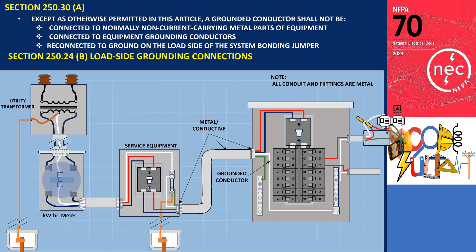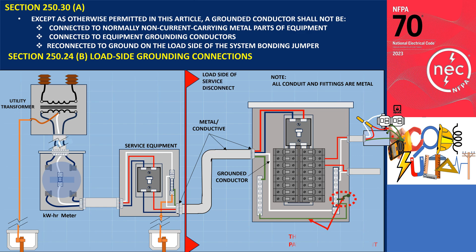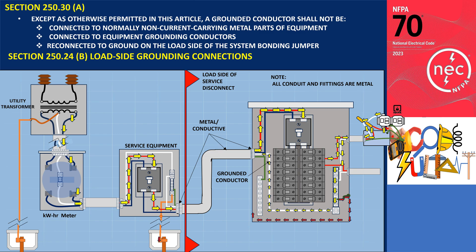This rule has been specified in section 250.24. This is not allowed because it introduces parallel paths for neutral current on the load side. When the grounded conductor, typically the neutral, is connected to the panel enclosure or any conductive metal components of electrical equipment at the load side of the service disconnect, it leads to the flow of neutral current into unintended paths such as metal piping, cable trays, cable sheaths, and similar pathways. This flow of neutral current is commonly referred to as an objectionable current. However, there is a section that allows the grounded conductor to be grounded again under specific conditions, which we will find out in the following sections.